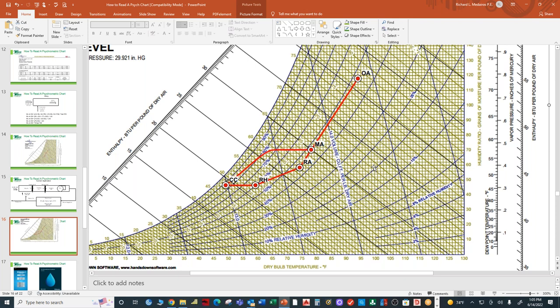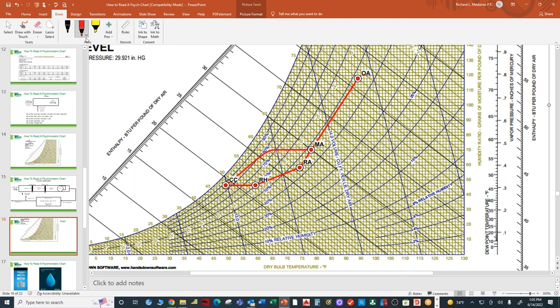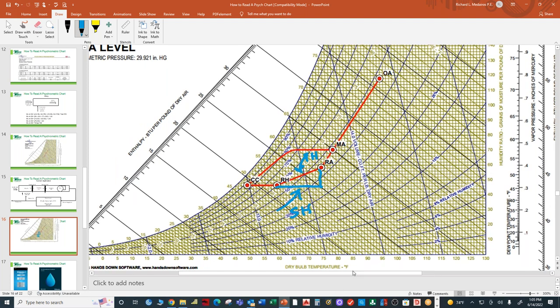They also calculate the sensible heat ratio. I'm going to change the color here to blue. So if I draw a horizontal line here and a vertical line here, this horizontal line is the sensible heat and the diagonal line is the total heat, TH. The sensible heat ratio is equal to the sensible heat divided by the total heat. In this particular example, that came out to be approximately 0.67.